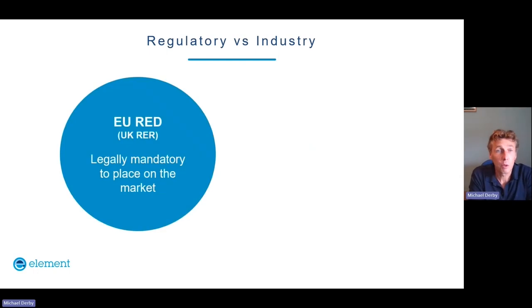Therefore it has at some point demonstrated that it can be placed on the market and can pass those tests. So similar to North America, over in Europe we have some industry requirements in addition to the regulatory. The CE marking, or the UKCA marking if you're using that for Great Britain, are the legal mandatory requirements for placing on the market.